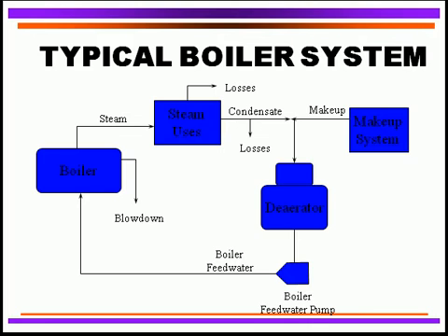The makeup water coming in at the upper right-hand corner of the diagram is prepared to whatever quality your boilers require — just like we talked about earlier on the guidelines. That preparation of the water either reduces our mineral content, our hardness, etc. That is blended with condensate coming back — the steam being condensed coming back — that mixes with the makeup water and goes to the deaerator, where we are actually trying to remove most of the dissolved gases from that particular makeup water — that feed water operation.